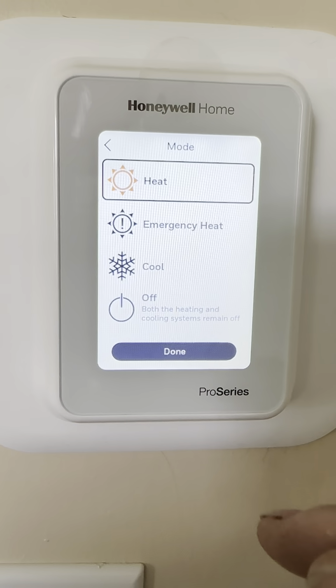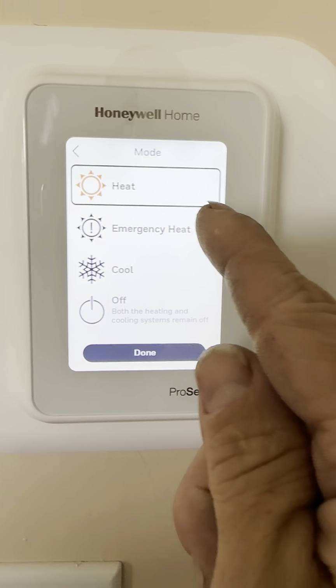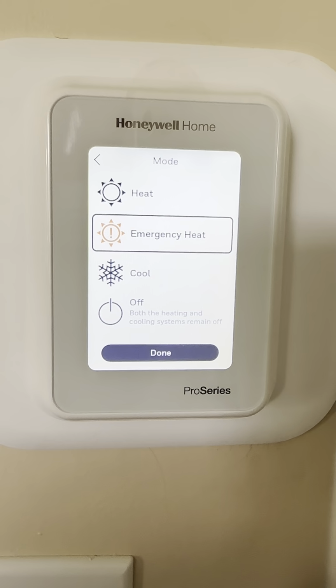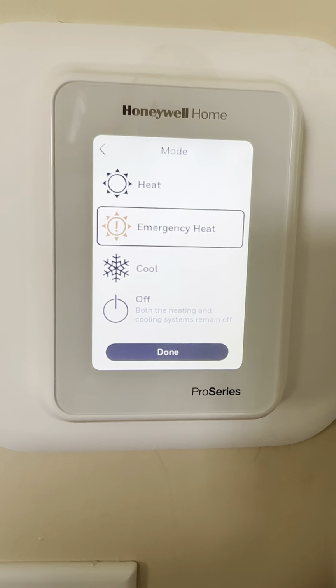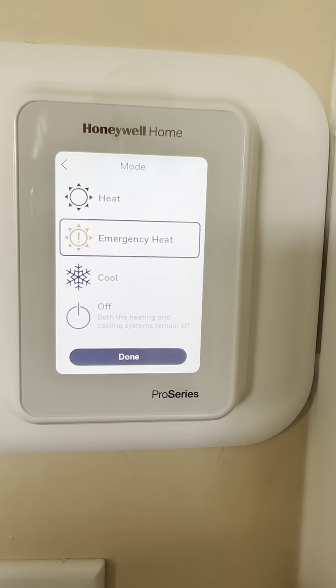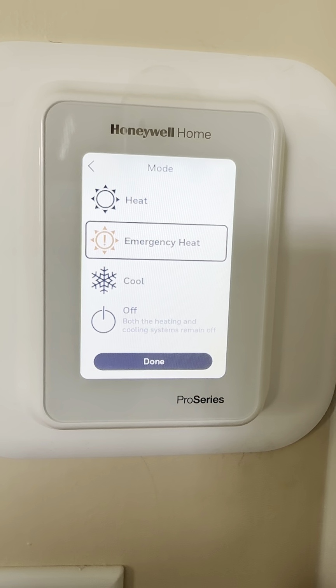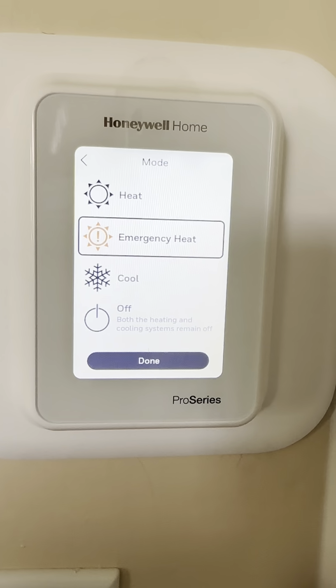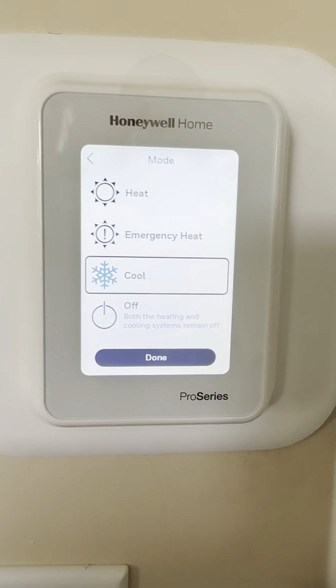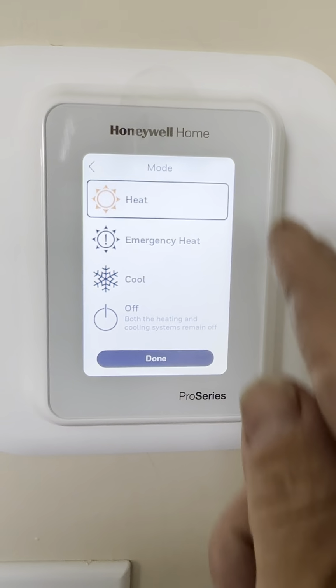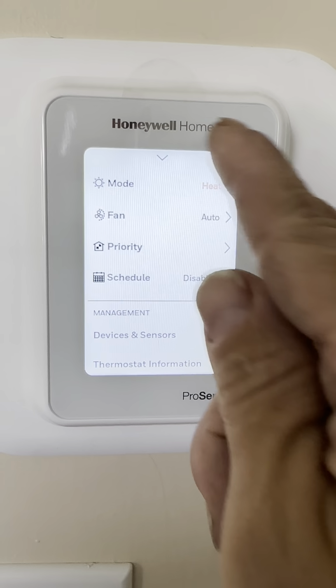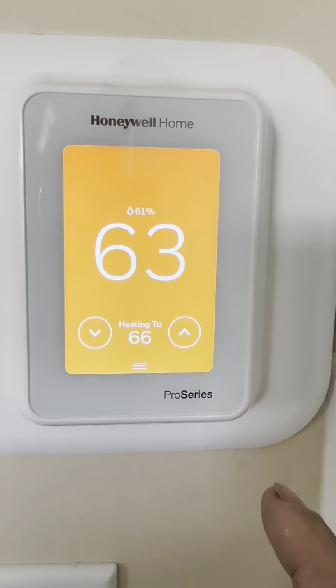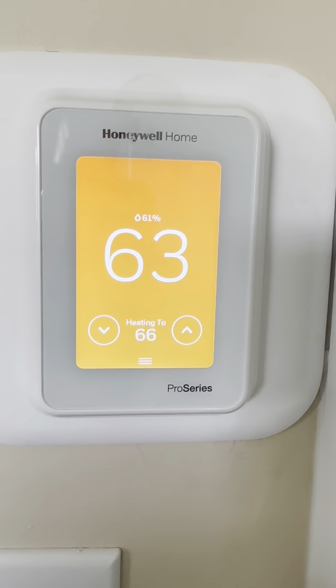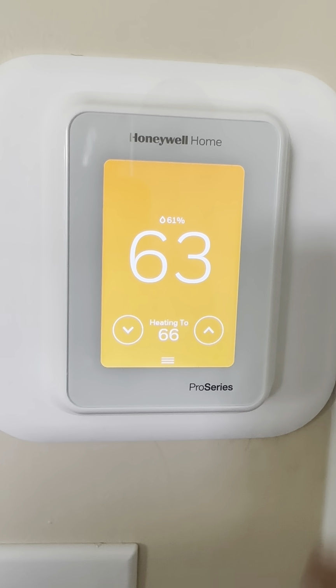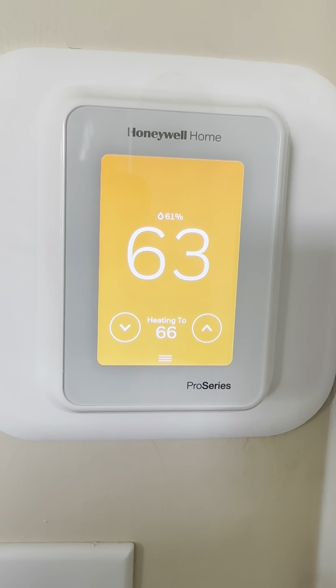So if we select heat, that's going to be the heat pump. If we go to emergency heat, that is going to be the electric backup, or if you have, say, an oil furnace or gas furnace, that would be what that is tied to at that time. And then, of course, cooling is your air conditioning. So we're gonna start with heat and see what this thing does. So we heard two little clicks there, and because our set point is higher than the current room temperature, we're going to activate the heat and bring things on.